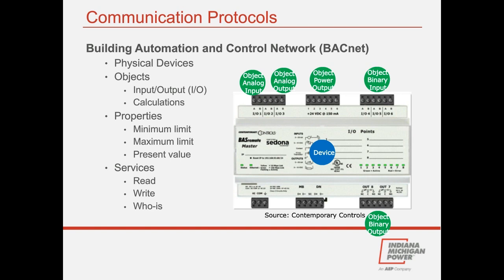When you get into objects, that's kind of an abstract concept, but it allows us to identify both the physical items like I/O points and non-physical concepts such as software and calculations happening within this box. This device has 8 points of input-output, so there'll be 8 objects created plus 1 for the device itself. BACnet defines over 24 standard objects, including things like loop, pulse, converters, calendars, that kind of thing. Each object type has a list of required properties and optional properties.